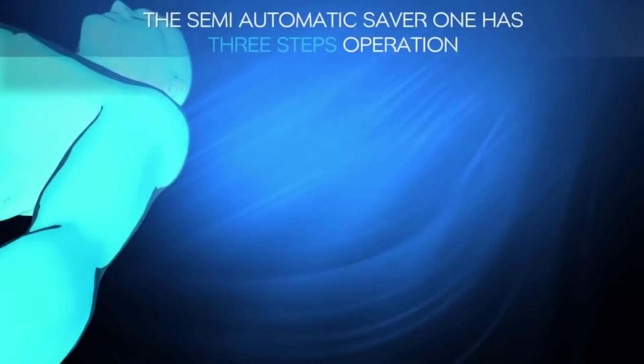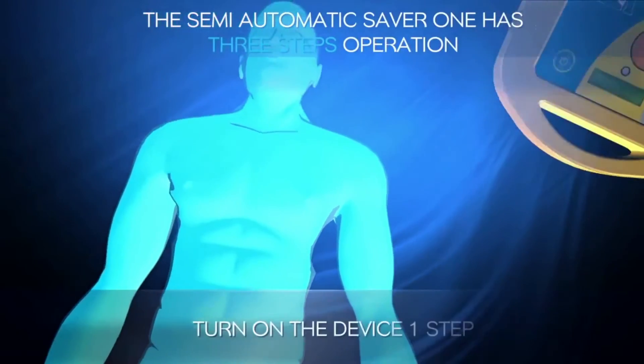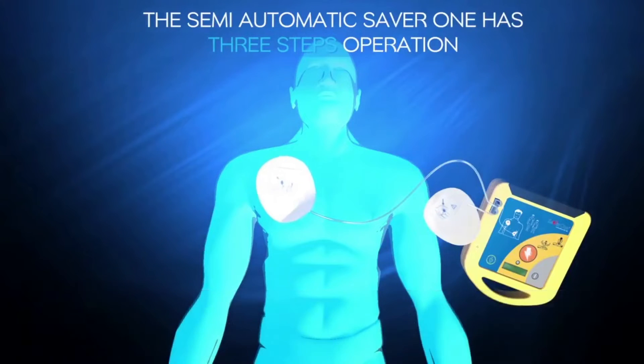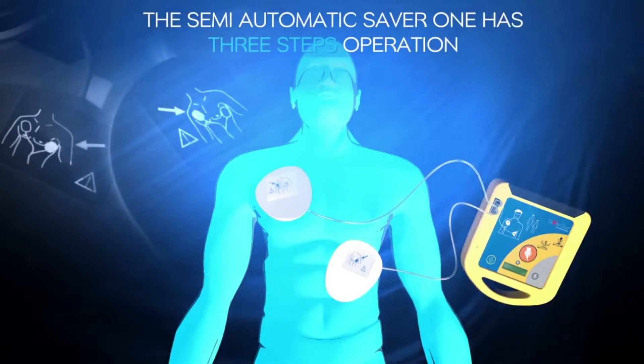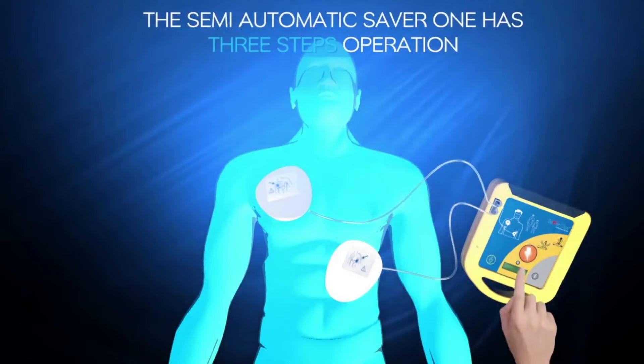The semi-automatic Saver One has three simple steps. Step one — turn on the device. Step two — place the two electrodes firmly to bare chest as shown in the picture. Step three — if shock is advised, you will hear: 'Do not touch patient. Analyzing heart rhythm. Stay clear of patient.